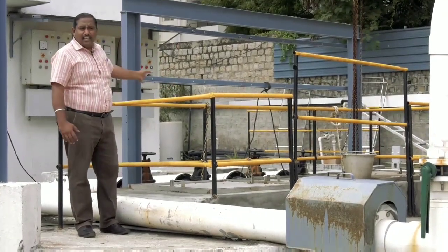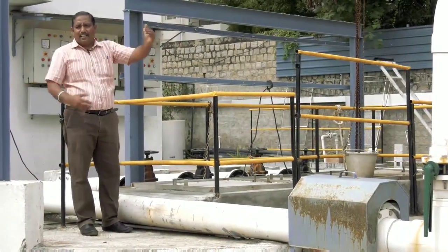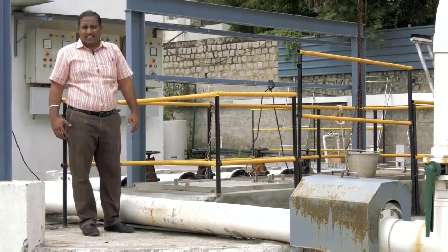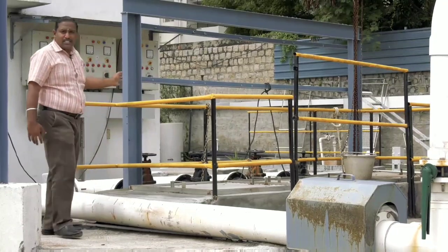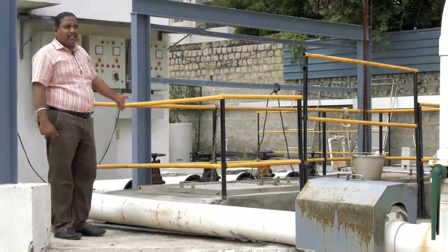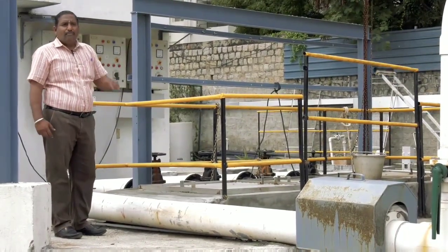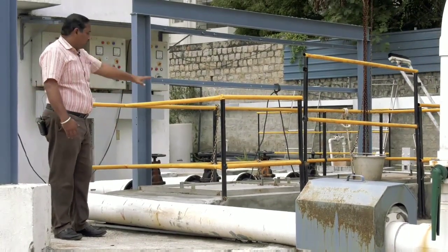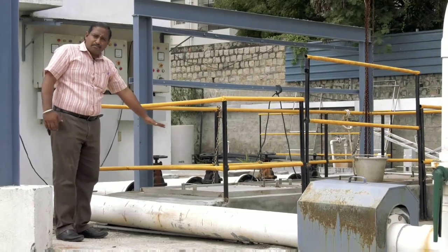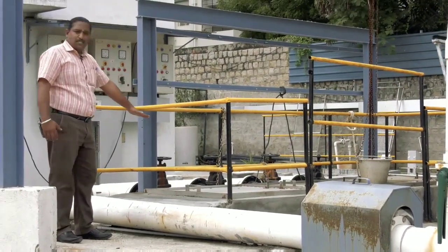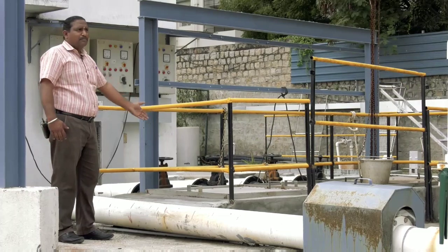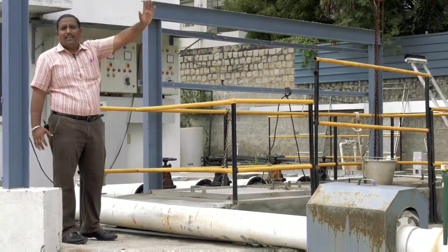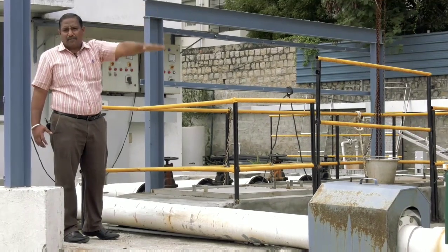These drives enable us to maintain the correct flow rate and also to minimize the current. These variable frequency drives are helpful in throttling the flow rate without an increase in the current. So it has the diffuser pipes along with the submersible pumps, which aid in transporting the water from this structure to the next part of the treatment process.